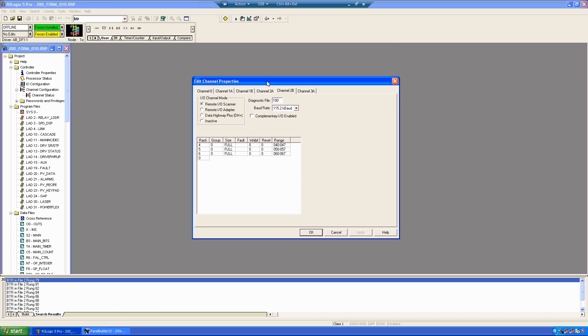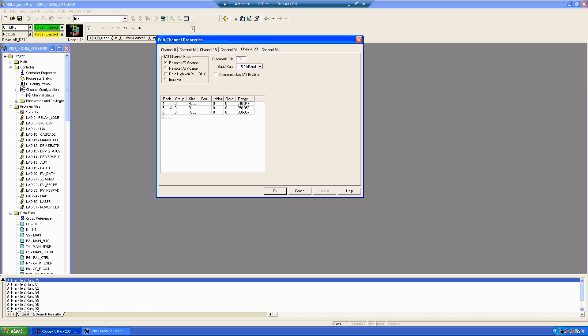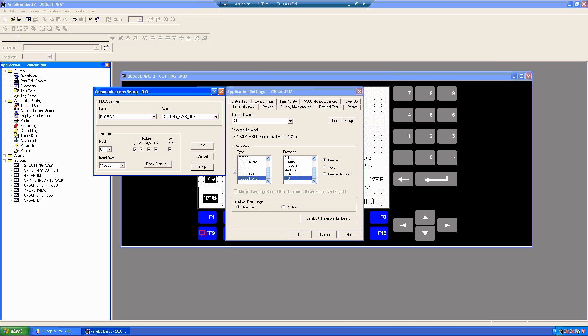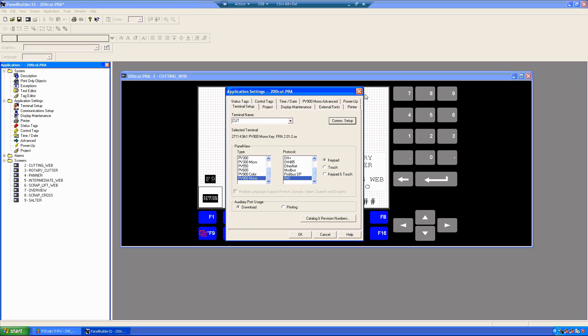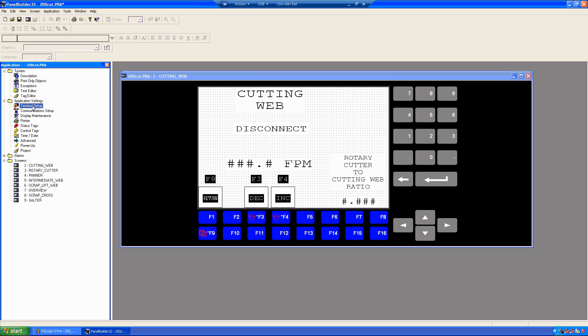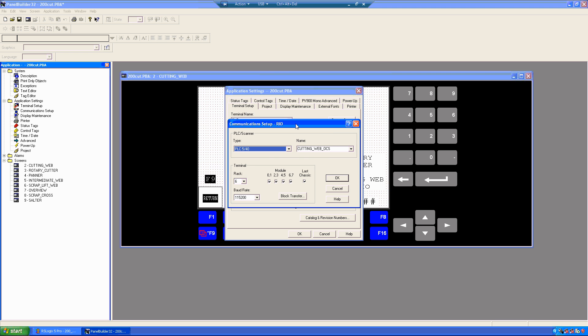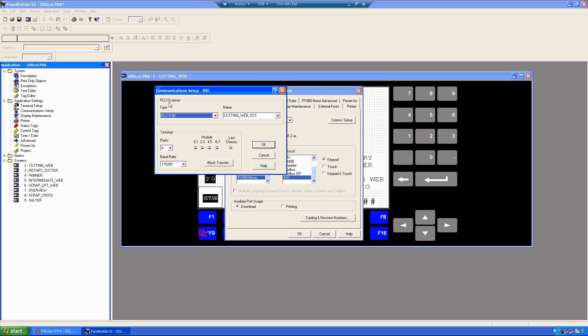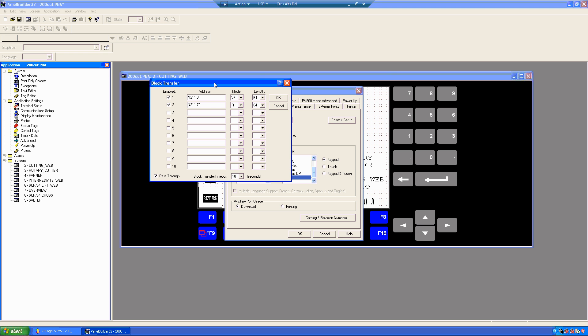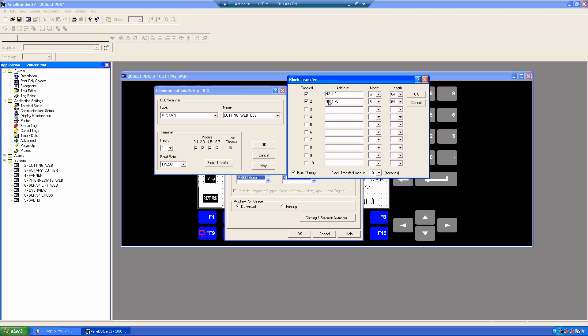In our case, I'm going to take just a quick shot at the panel view configuration here. So, I have the panel builder program open, and just to give you an idea. So, this one's in 32. So, if I go to terminal setup, and it is a RIO panel view. If I go to comm setup, this is basically saying this is the PLC it's going to talk to. That's the name it's going to talk to. And this is the terminal information. So, it's going to rack 6. So, effectively we're looking at 6.